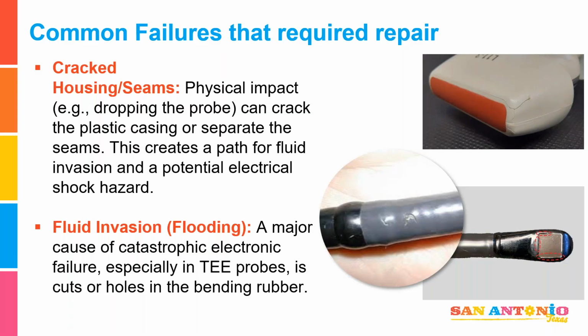So stuff like this we can fix. It's fairly easy. There's a lot of third-party people, OEMs, that can take care of problems like this for you. Find a trusted partner and get it taken care of when it's affordable. Fluid invasion, a major problem with TEE probes especially, but even the one above with a crack in it, once it gets fluid in there and it starts wearing away on the electrical components, it causes corrosion. It's a big problem. Major cause of catastrophic electronic failure. It's just a problem. Earlier you can detect it and get it fixed, the better it is. The longer you wait, the more expensive it's going to be.